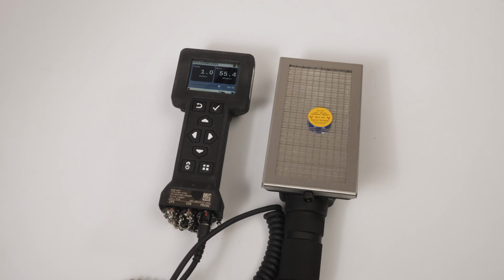Verify the radiation reading value falls within the range of 13 to 95 kilocounts. At the end of the scaler duration, the radiation reading will not change. The base unit will continue to monitor for radiation in the background. If you want to see active radiation readings again, you must change the data log mode back to auto threshold or auto interval. Let's go ahead and change the settings back to auto threshold data log mode.